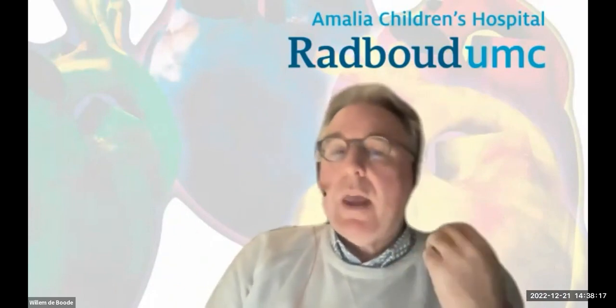I think it's very important that you have a correct position of the electrodes, because if there's a change in the distance between the electrodes, that will affect the measurement, and that's one of the problems, because the electrodes are not designed specifically for newborn infants, especially not for preterm infants. So they're rather large, and everyone is trying to adjust and adapt. But it's also the condition of the patients. If you've got a patient with a lot of edema, that will also influence the bioimpedance. If the patient is on high frequency ventilation, that will also influence your measurements. So all these conditions are important to consider if you want to use or are using these types of cardiac output monitors.